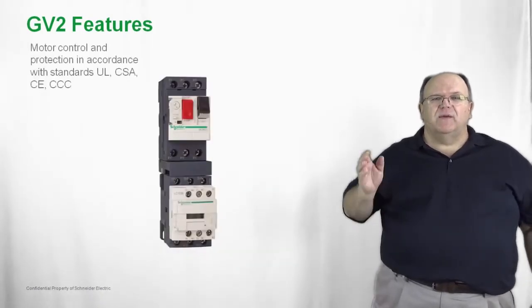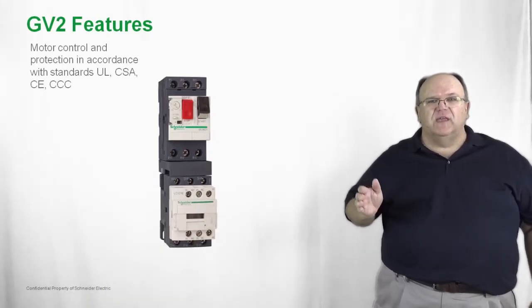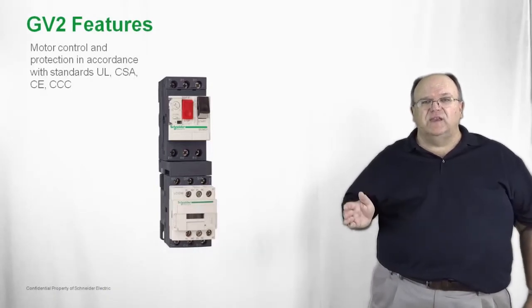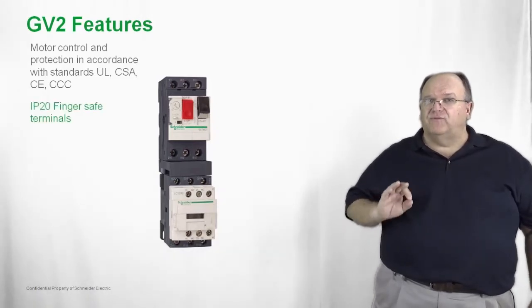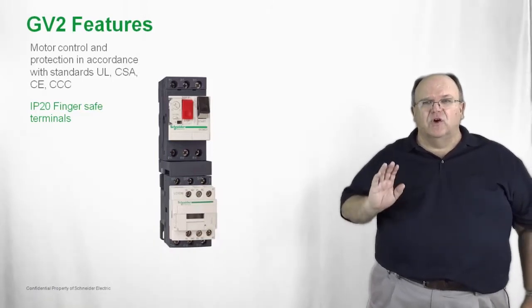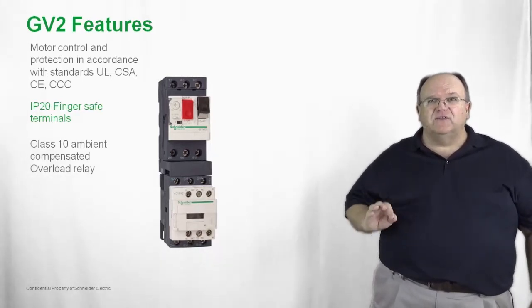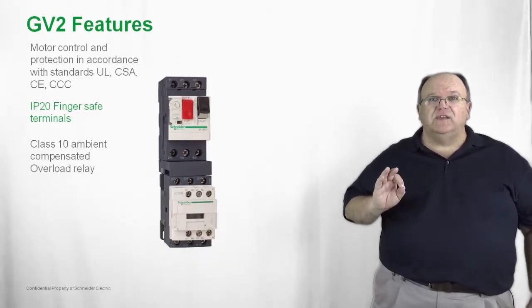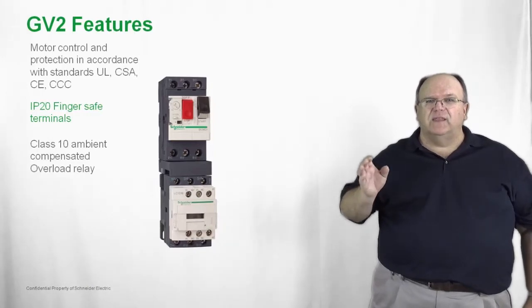Here we have the GV2ME associated with the contactor — in this case the TeSys D — and this product is in full compliance with North American standards, international standards such as the CE mark, and also the CCC mark for the Chinese marketplace. All the products are IP20 or finger safe just like the contactors, so no exposed current carrying parts. The overload protection provided with the GV2 product is a Class 10 ambient compensated bi-metallic overload relay, giving you the same reliable protection you expect from the LRD overloads, all incorporated into one device.